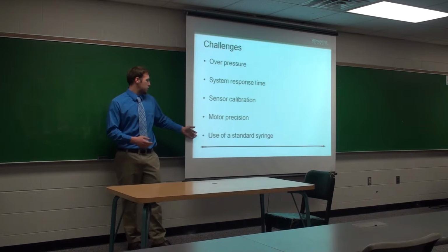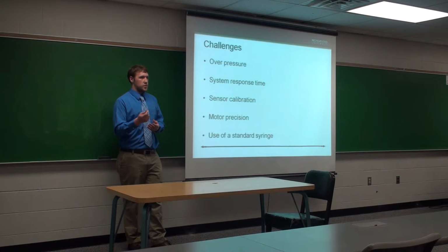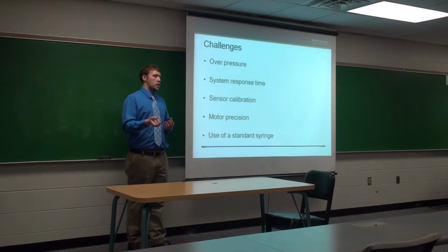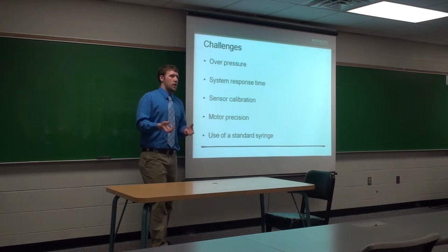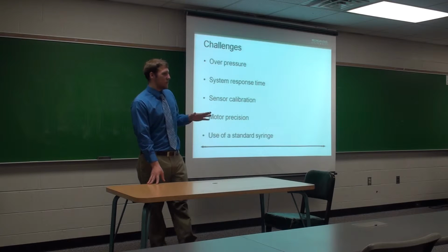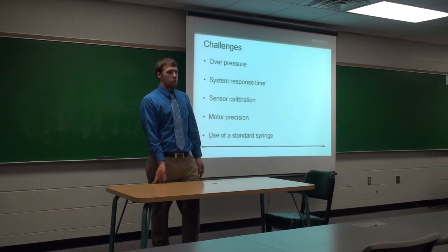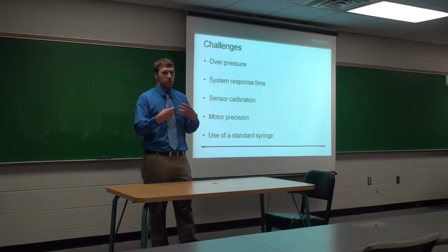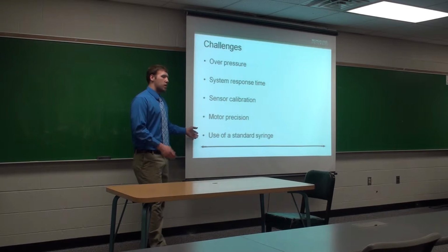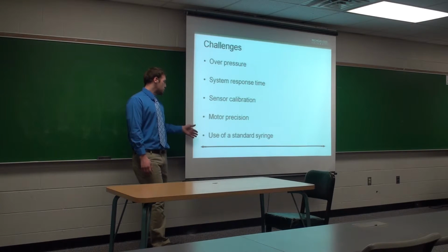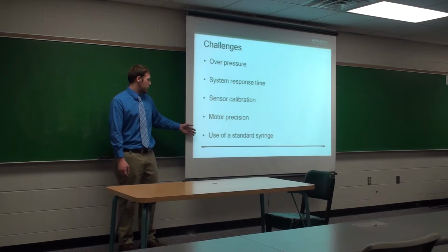And we also touched on the use of a standard syringe. We said that if the rubber dries out on the stopper, it will cause problems with the system, such as leaks, and also the lifetime of these syringes is roughly 12 tests. So if we can get through 12 tests every time, they'll just replace it every 12th test, which will be a good idea, so we don't meet up with any of these problems, such as the sticking of the rubber stopper.